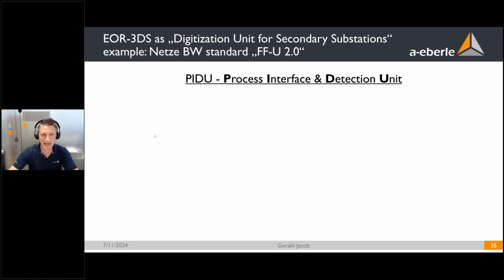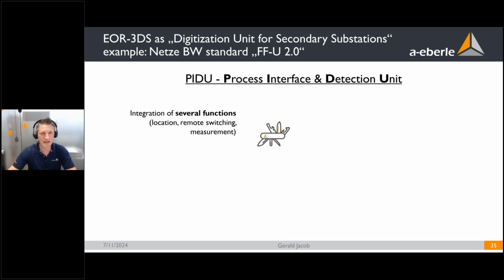In the tender, they required a so-called process interface and detection unit. This indicates they looked for a device that was not only an earth fault and short circuit indicator, a detection unit, but a process interface. What did they mean by that? The device they looked for should be capable not only of location and simple measurement, but they wanted precise measurement and also this remote switching functionality, of course. In these very important secondary substations and critical nodes in the grid, they want to have remote access to the load breaking switches.